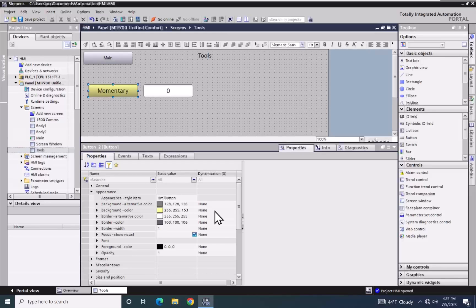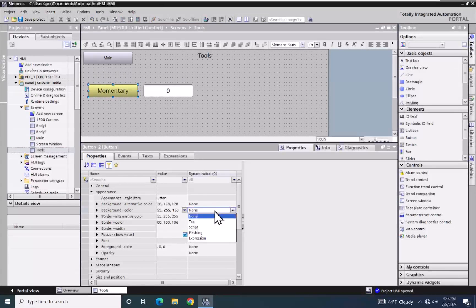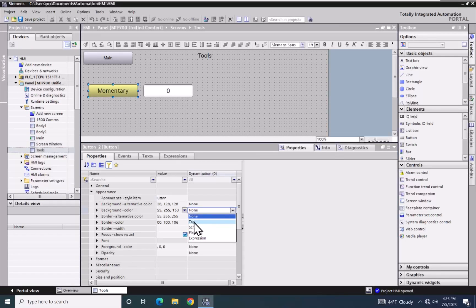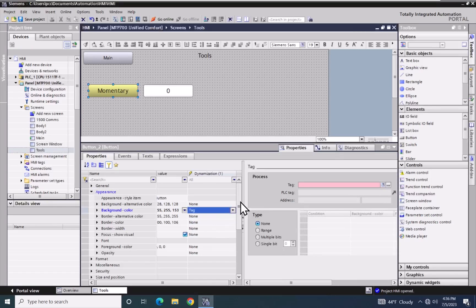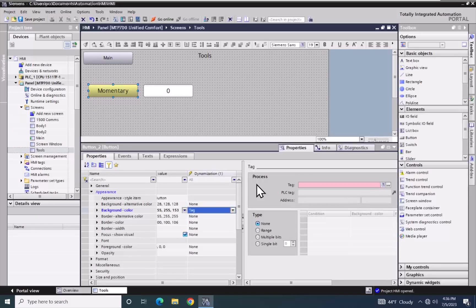The dynamization column is where you can pick how you are going to dynamically change the background color. I'm going to click in this area and in the drop down I've got a variety of choices to control how the background color is going to be dynamically controlled. In this lesson we are going to cover a tag animation, so I'm going to select tag and we're going to use the bool tag underscore one to control the animation of whether the color is going to be changed on the push button.